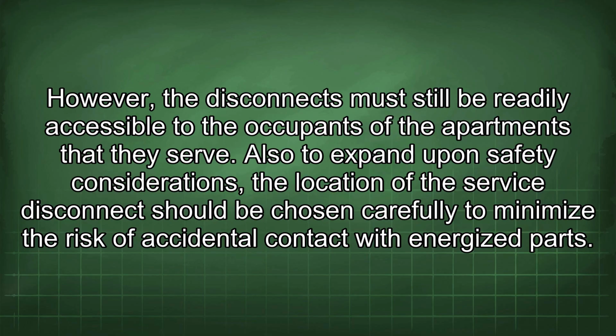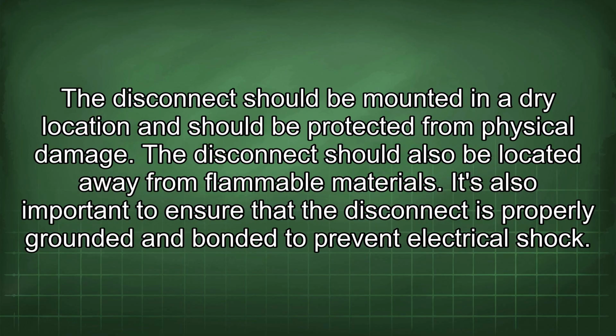Also, to expand upon safety considerations, the location of the service disconnect should be chosen carefully to minimize the risk of accidental contact with energized parts. The disconnect should be mounted in a dry location and should be protected from physical damage. The disconnect should also be located away from flammable materials. It's also important to ensure that the disconnect is properly grounded and bonded to prevent electrical shock.